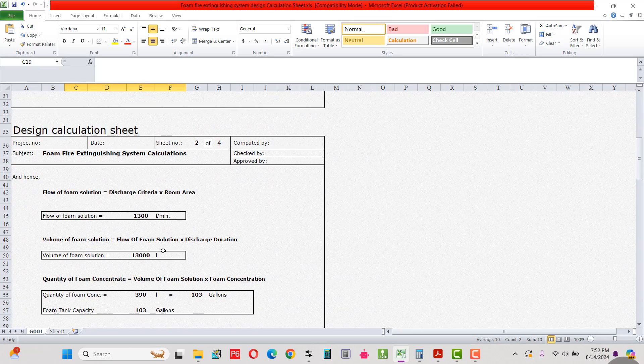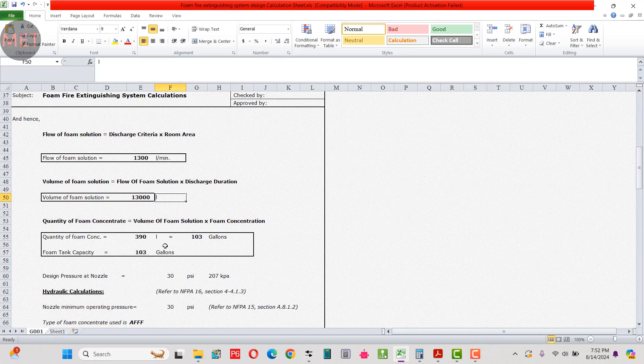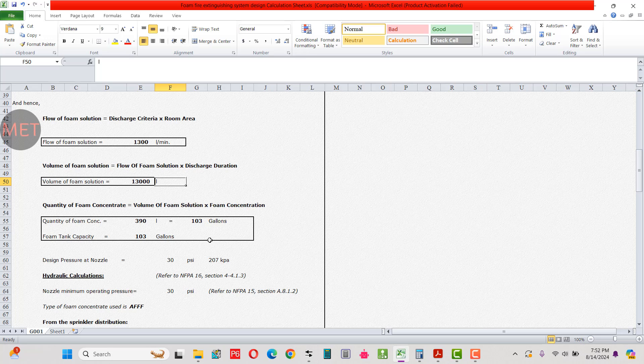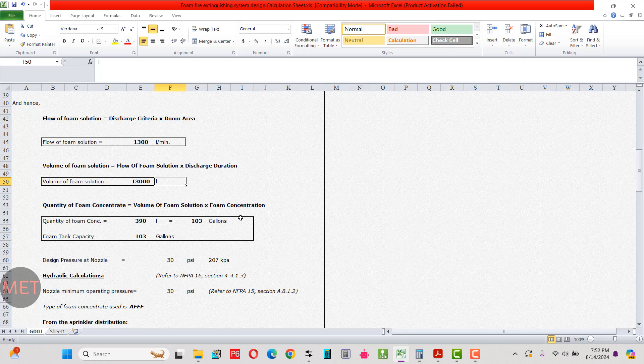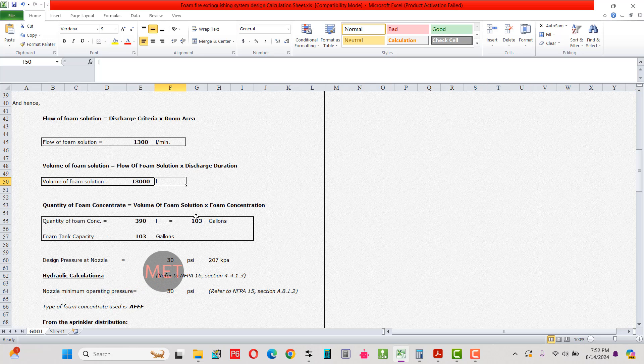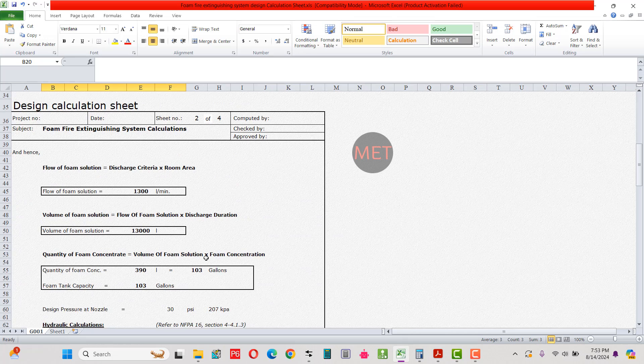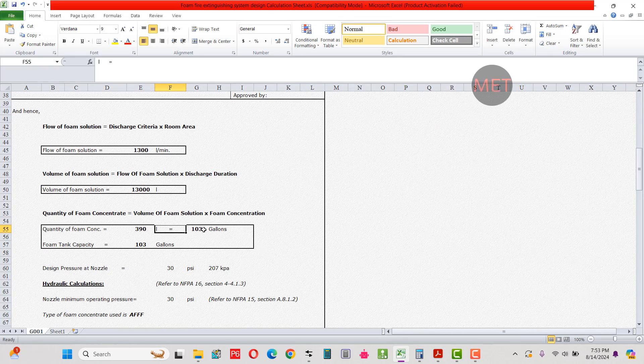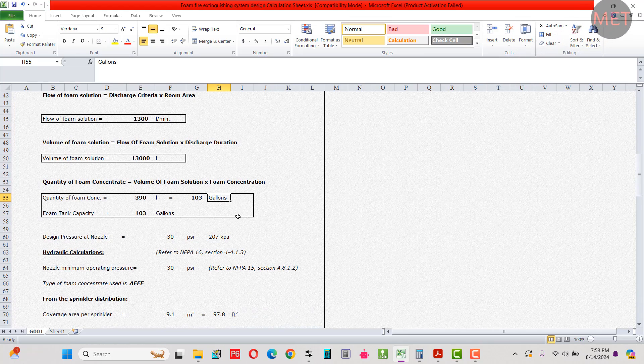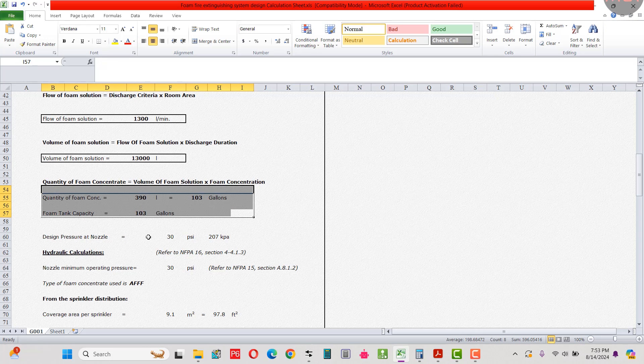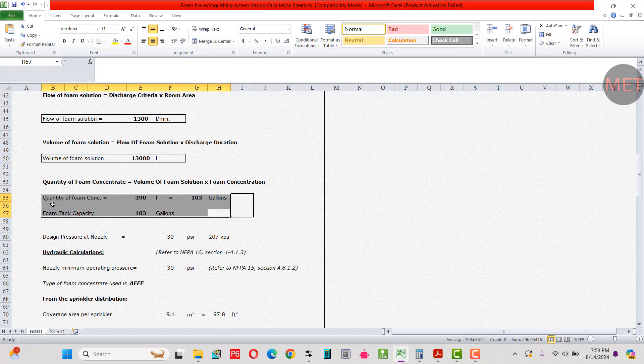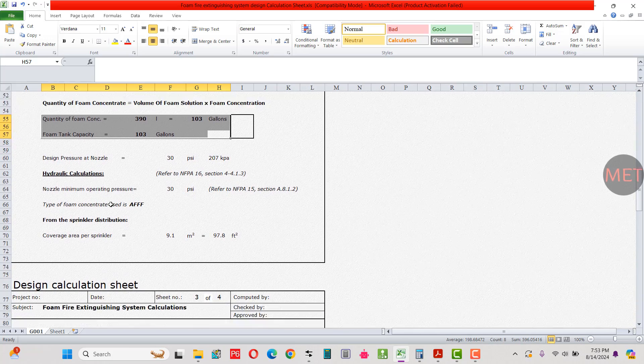Next, the quantity of foam concentrate equals volume of foam solution × foam concentration: 13,000 liters × 3% = 390 liters, which equals 103 gallons. So the initial foam tank capacity is 103 gallons. Note that this is not the final foam tank capacity — it will be revised based on the third parameter, which I'll explain later.